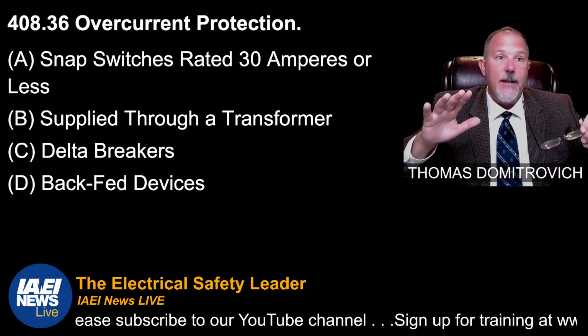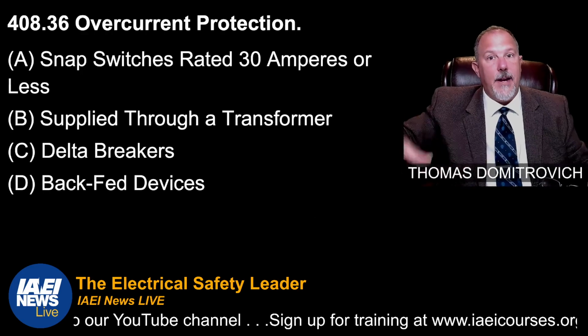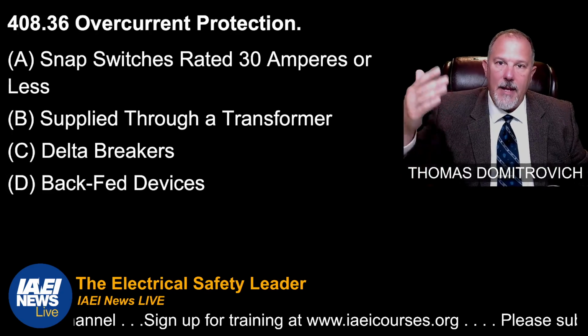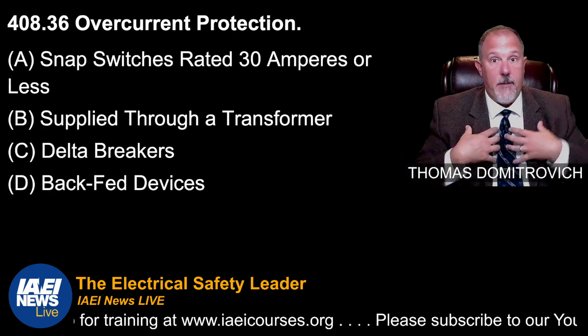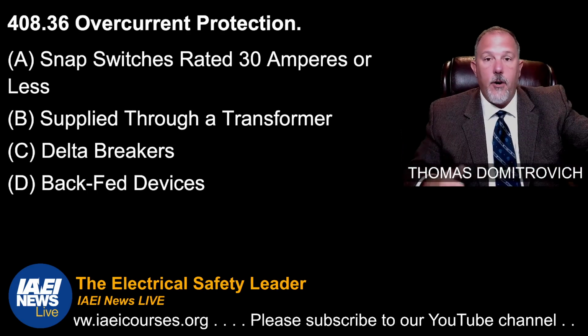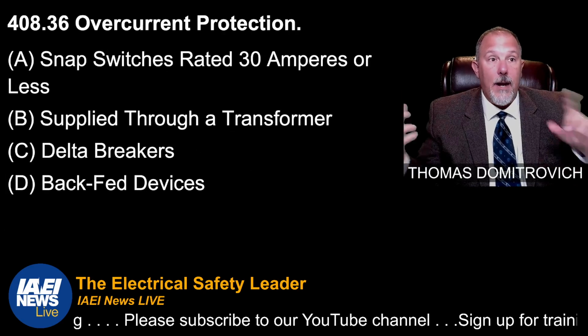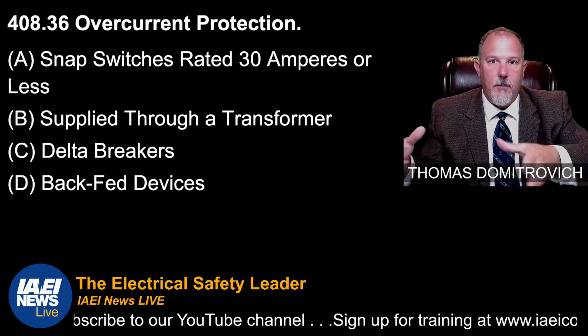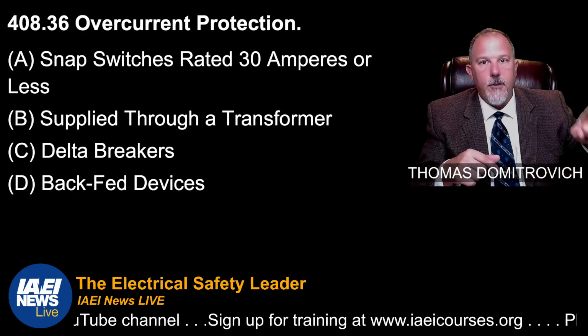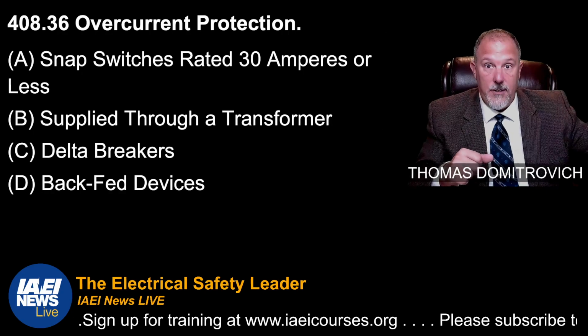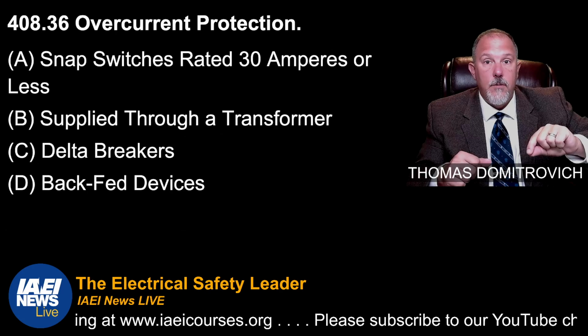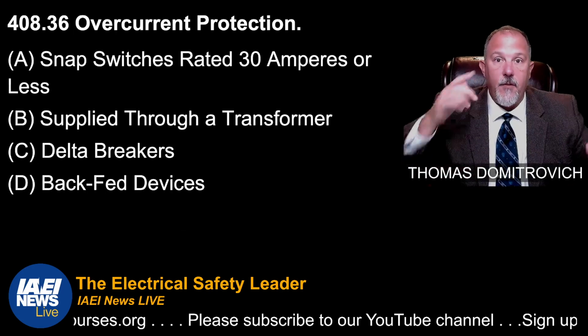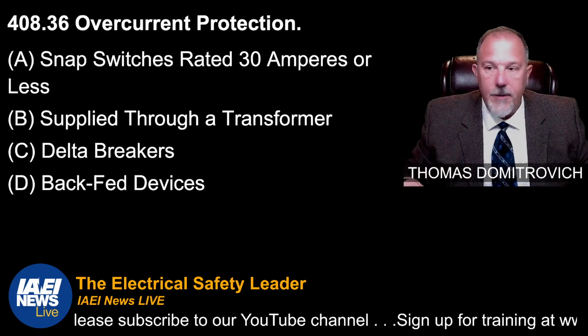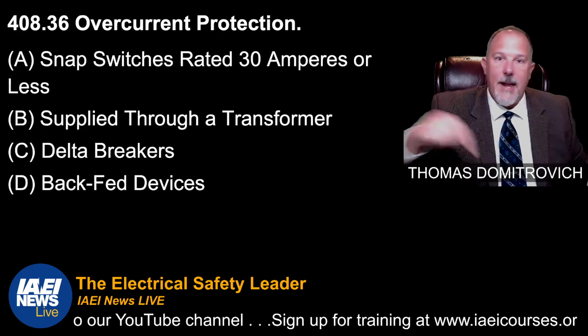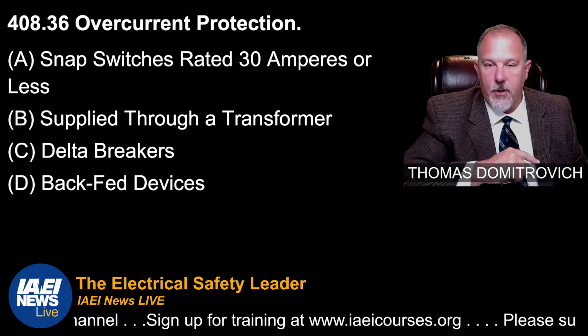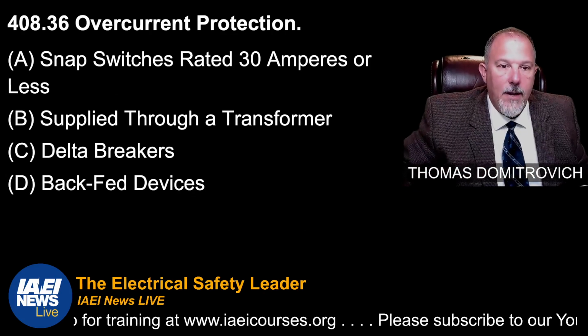So it's very rare that I have ever seen anything that doesn't violate the NEC that didn't have a main. The best design, in my opinion, is to come off the secondary of a transformer, land on a switch, and then go to a main lug only panel board. Why do I love that one? Because the incident energy in that panel board is going to be based upon the overcurrent device on the secondary of the transformer, which is in that switch. And that will reduce the severity, as long as the available fault current and the arcing current are in the right region of that fuse, obviously. But your likelihood of that happening is much greater than if you're relying on the primary overcurrent protective device of the transformer. Just saying.